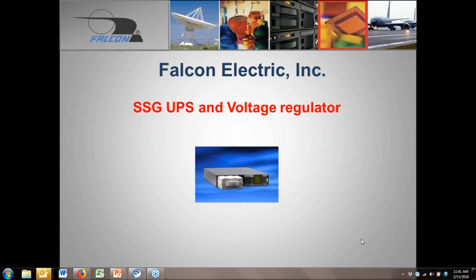Next question, though, is how does deep discharge affect battery performance and life? The deep discharge cycles are not affected. Again, we have a system that does not allow deep discharging of the batteries. We cut off at 10 volts on the batteries. Any battery that has a deep discharge will obviously decrease in life over time, especially if they go down that far. But we don't go past 10 volts. That is CPU controlled from our UPS, which allows longer life from the batteries, and obviously with the larger amount of cycles, you definitely will get that life because you're not going too deep into the battery.